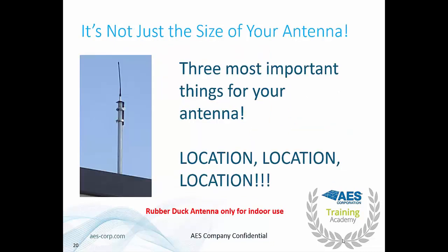So what are the three most important things for your antenna? Location, location, location. Just like if you were to start a restaurant, it is very important that you choose the proper location for the antenna. The subscriber can be almost anywhere as long as you're not using the dialer. If you are using the dialer, it needs to be within 20 feet of the fire alarm panel.